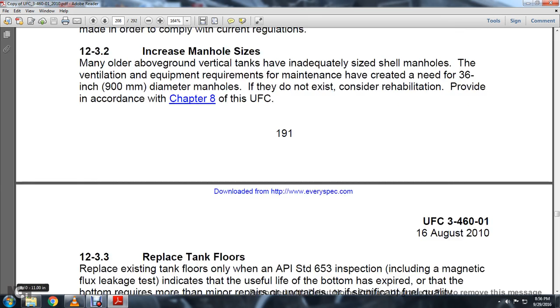12.3.3 Replacing the tank floor. Replace tank floors only when an API Standard 653 inspection, including a magnetic flux leakage test, indicates the life of the bottom has expired, the bottom requires more than minor repairs, upgrades are needed, or fuel quality problems from standing water exist. Contact the service headquarters for guidance whenever a tank bottom replacement should be completed. Comply with current design standards, including double bottom and single bottom liner.